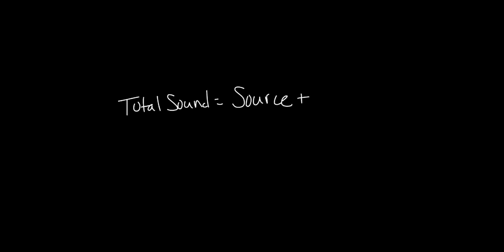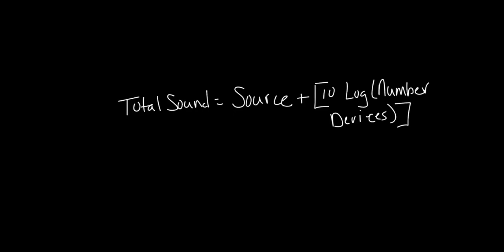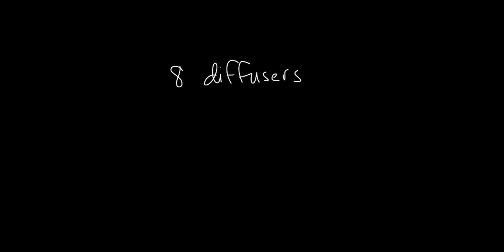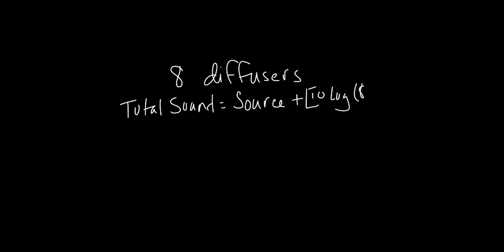Well first of all, let's look at the additive effect. We can always multiply sound sources by using this formula. The total sound is equal to the sound of a single device plus 10 times the log of the total number of devices. Let's say that we have 8 of these diffusers in our array. The total sound equals the source plus 10 times the log of 8, which tells us to add 9 to the original source.